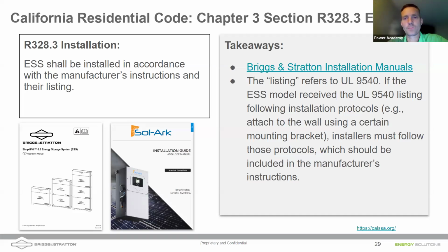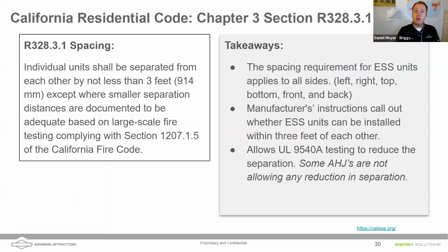Good point. Individual units shall be separated by not less than 3 feet, except where 9540A testing has shown a reduction is allowed. Notably, many jurisdictions around the country, including San Jose, California, don't care if you've tested with less spacing—they still require the full 3 feet. At the end of the day, the rules lie with your AHJ, so talking to them ahead of time helps avoid costly reconfigurations at inspection.